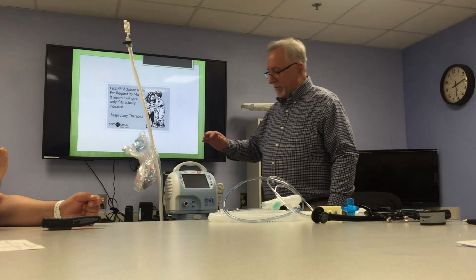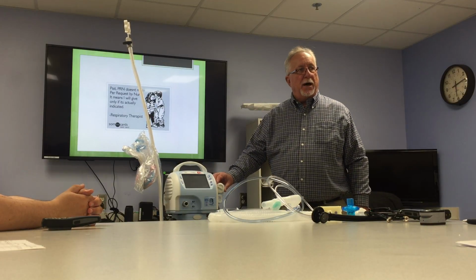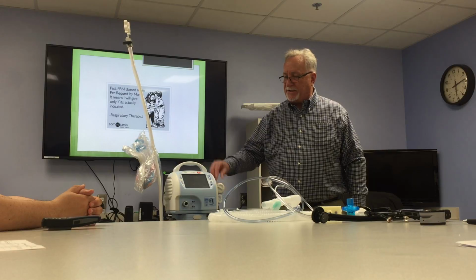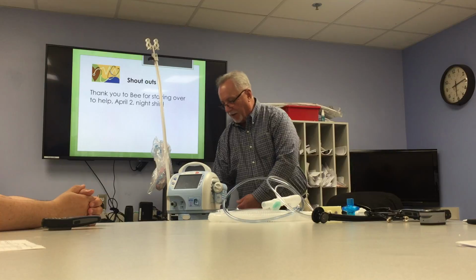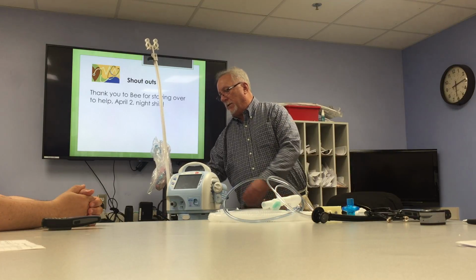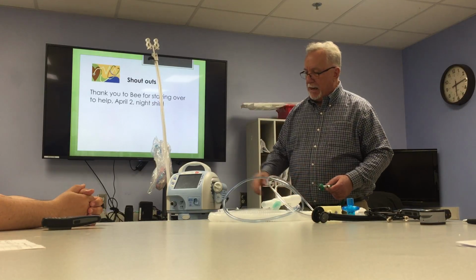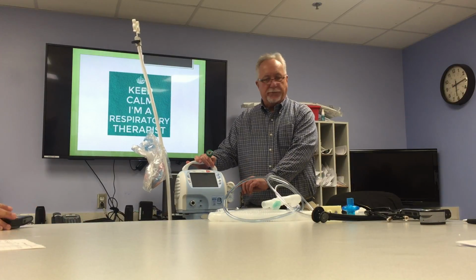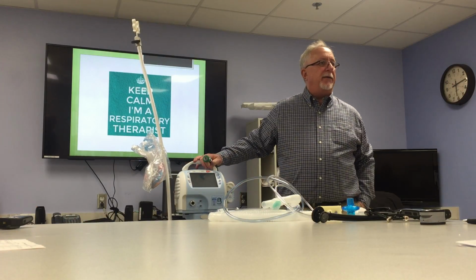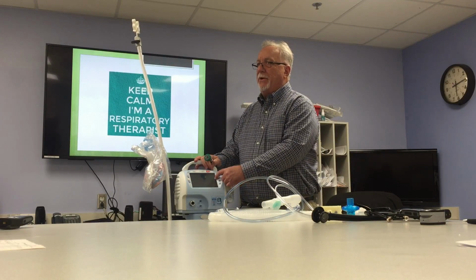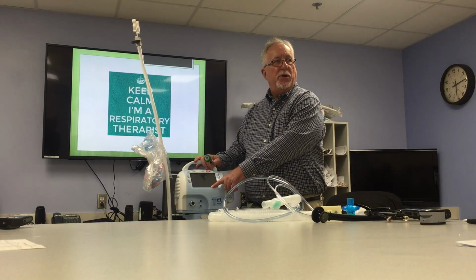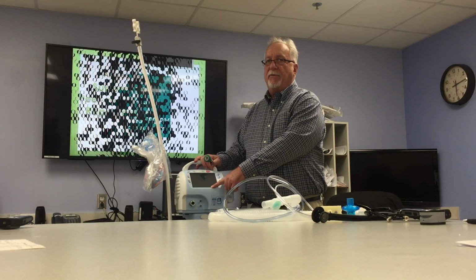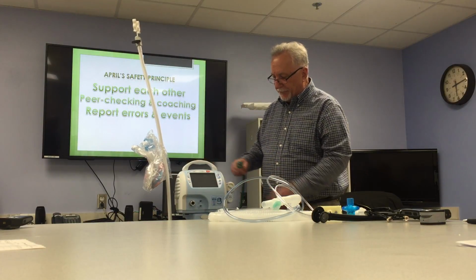the ventilator. But on the side here, you have your mixing valve that attaches to the side of the ventilator. It's basically a blender. You have a 50 psi hookup. You can put a quick connect on there if you want to go from wall to tank. There's a dial on the front here, and on top here there's a scale that goes from 21 to 100%. Okay. Nice thing about it, it has a built-in O2 analyzer, so it'll give you a readout on the front panel of the ventilator. Okay, easy enough.